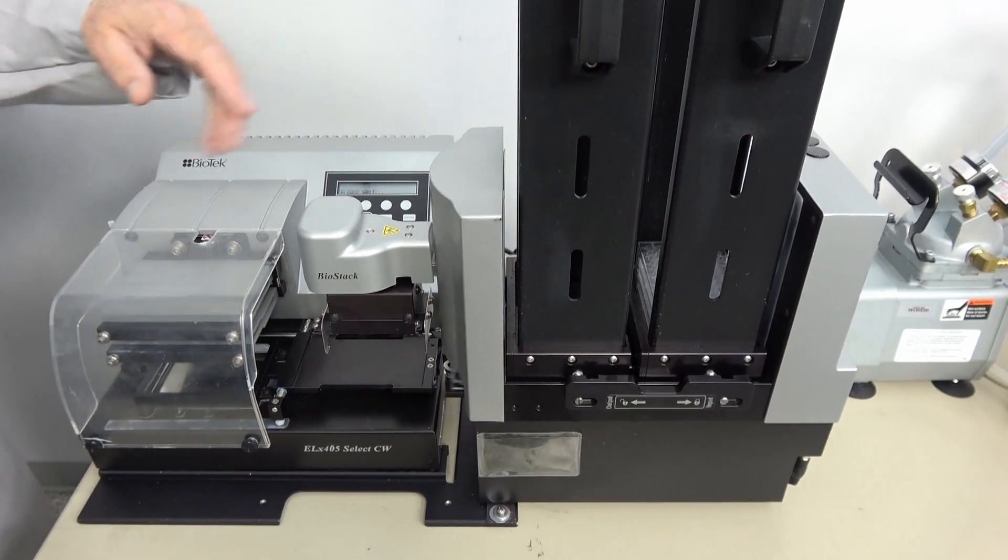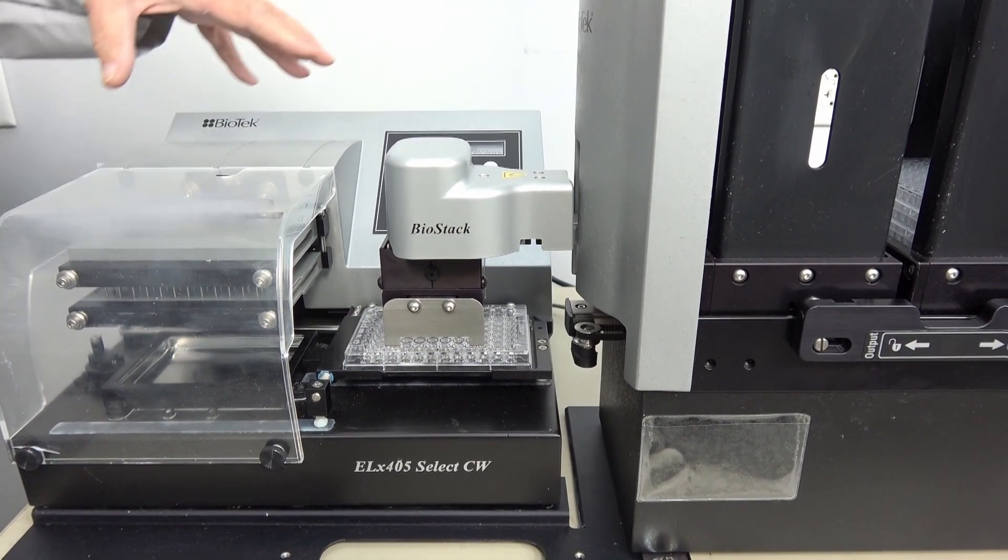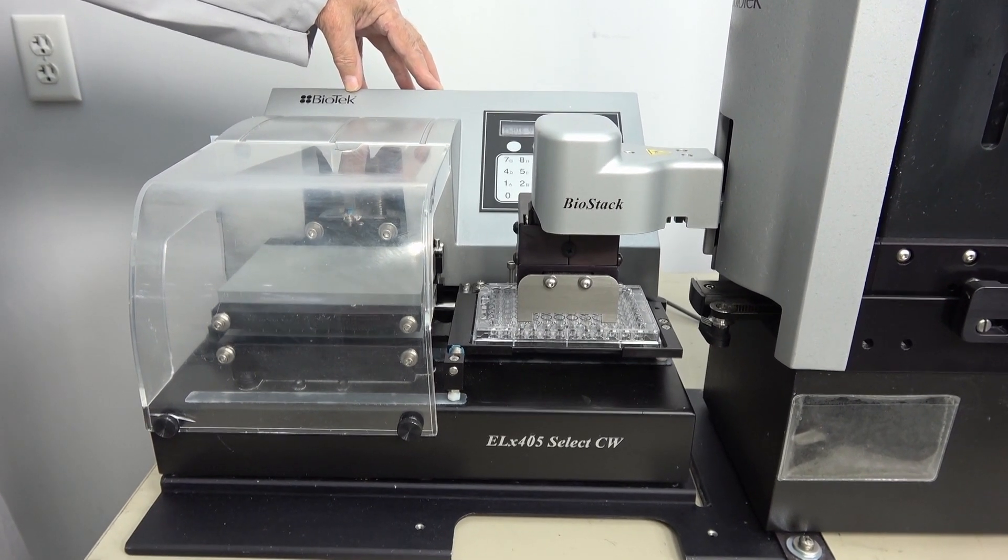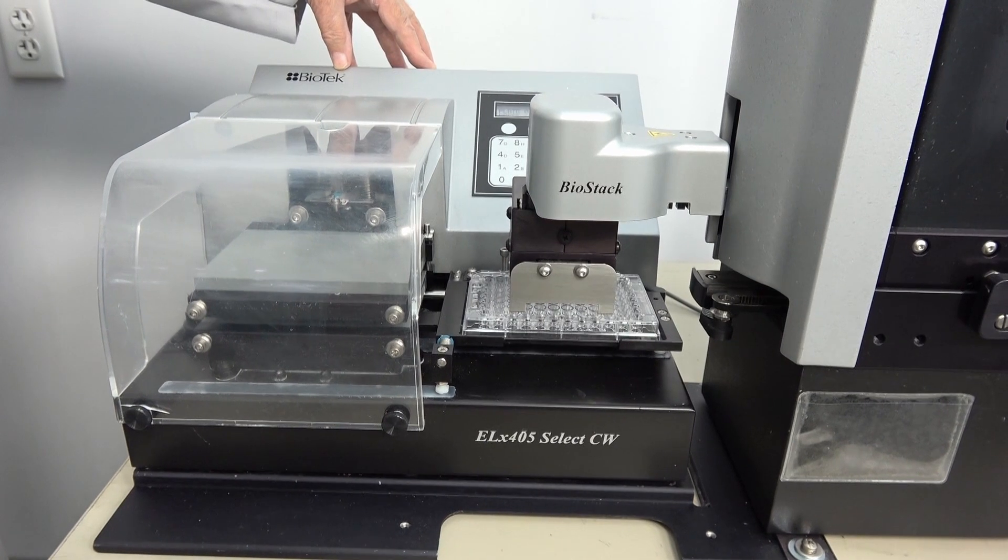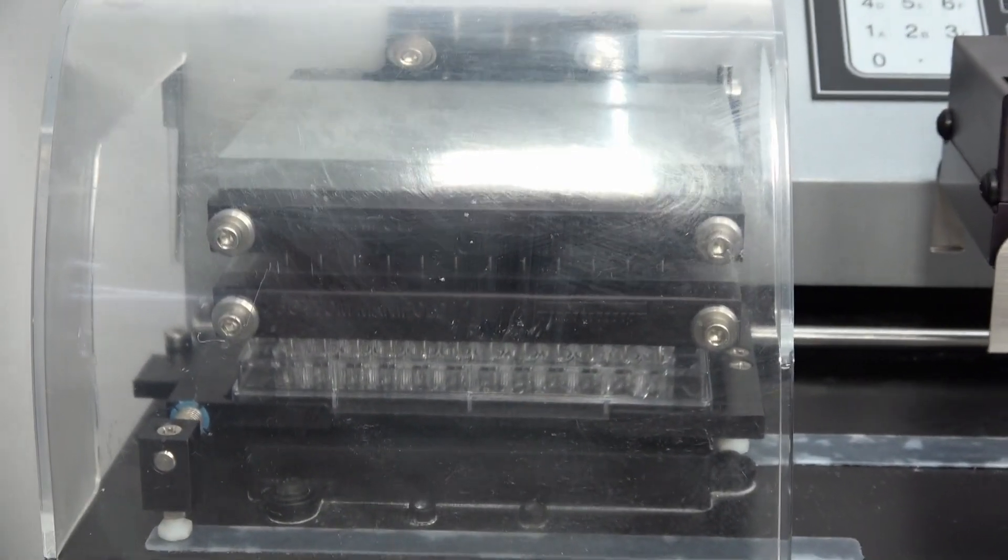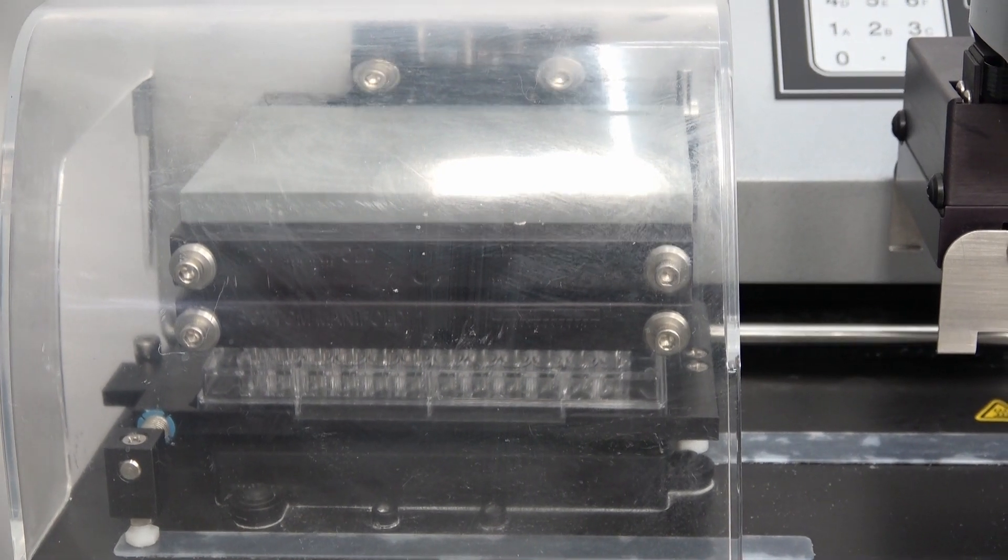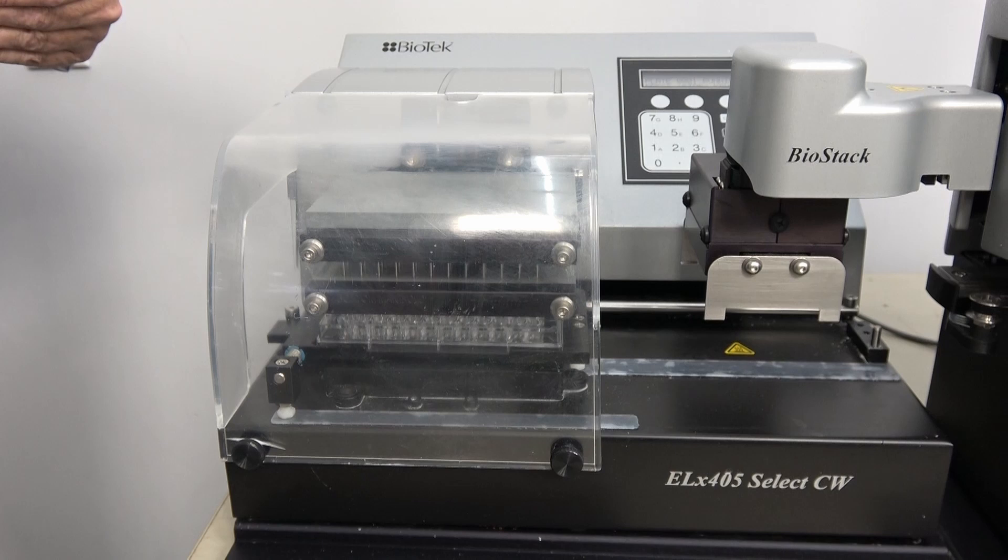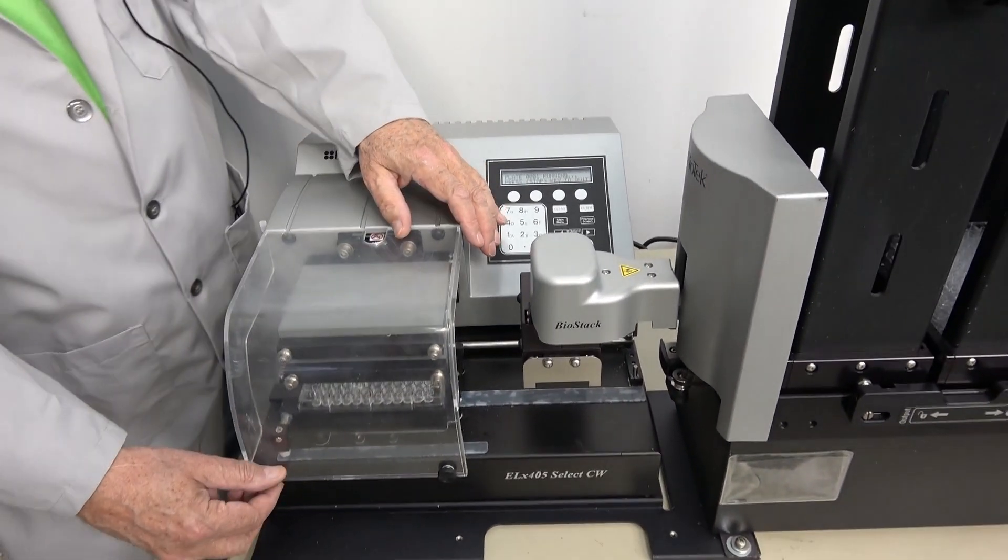It lowers the plate out, brings it out. Drops into place. As you hear there, the vacuum pump clicks on. It goes ahead and starts priming. Gets ready for the wash. You can hear it doing the aspiration. You can set this up to do several cycles on the wash. One, two, three. I think you can do up to seven cycles. How much liquid you want to use in the wash. In addition to doing washing, it also dispenses. So again, you have similar options on that as well.